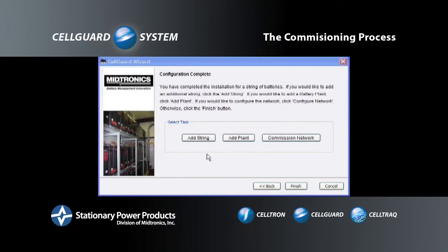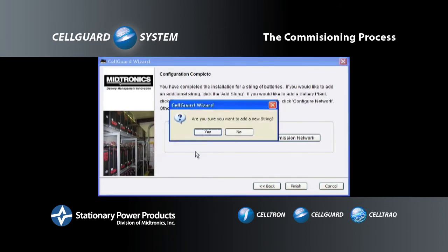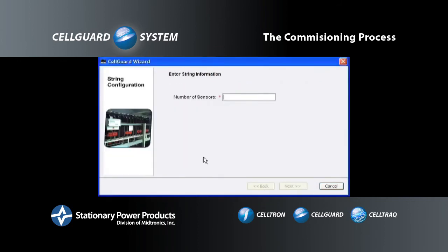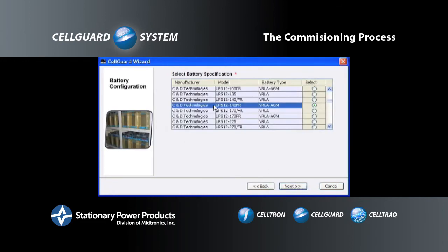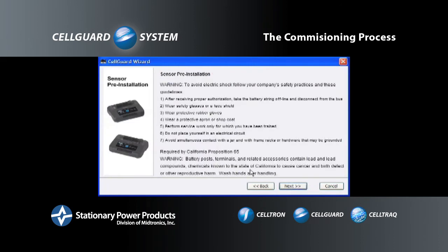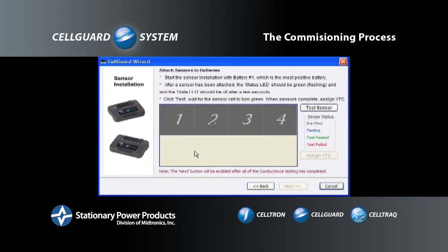To commission the hardware for another string from the same power plant to the existing BCU, click Add String. A message will pop up asking, "Are you sure you want to add a new string?" Click Yes to proceed. The number of sensors is 4 again. Click Next. This string consists of the same battery model. Click Next. Once again, read over the safety precautions. Click Next. Now, start the same process for commissioning the sensors.